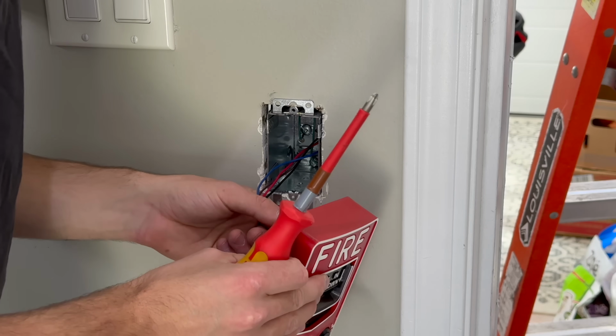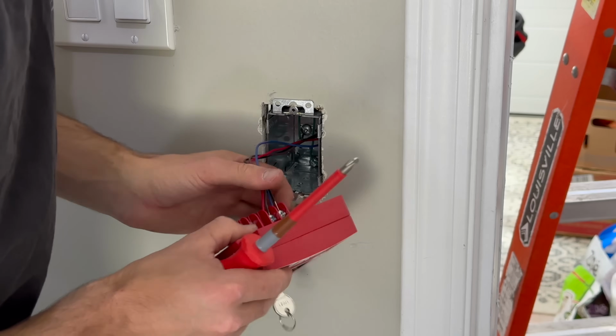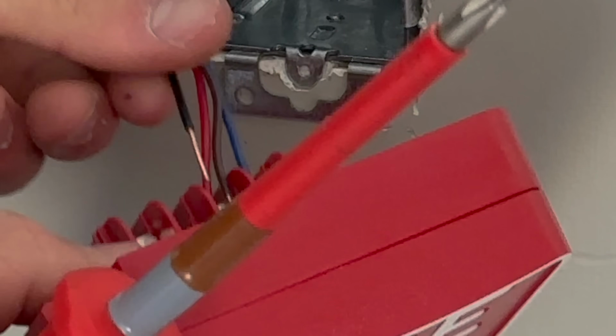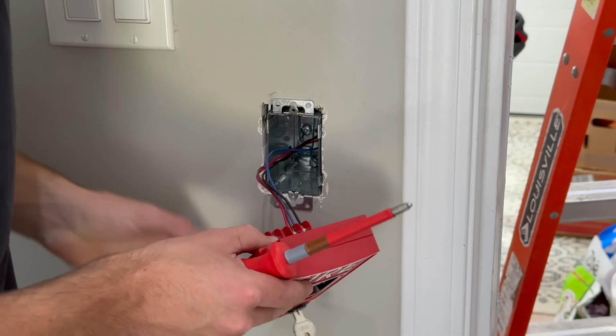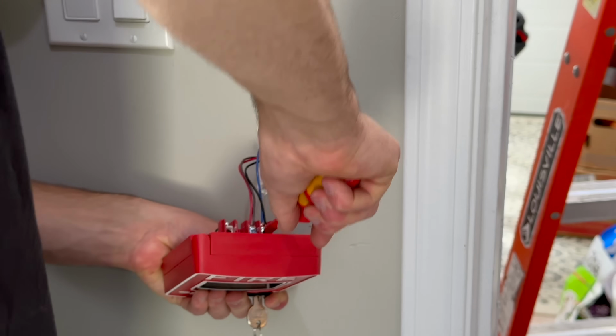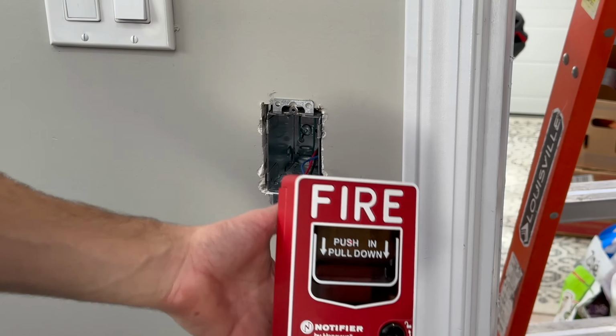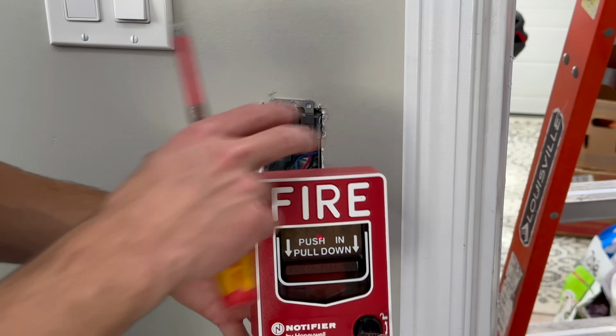The reason we're in trouble is just because we are now initializing. Oops, shorted out our SLC if you saw that little spark there. It's okay, it has isolators. It was probably fast enough, nothing even tripped, but if it did, it would have only lost the first floor. Contrary to popular belief, shorting out the SLC does not damage anything. There you go. That is now pulling red, as you may be able to see. It'll go green eventually once it's initialized.